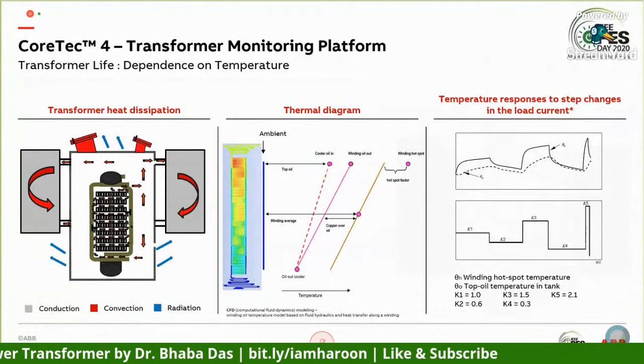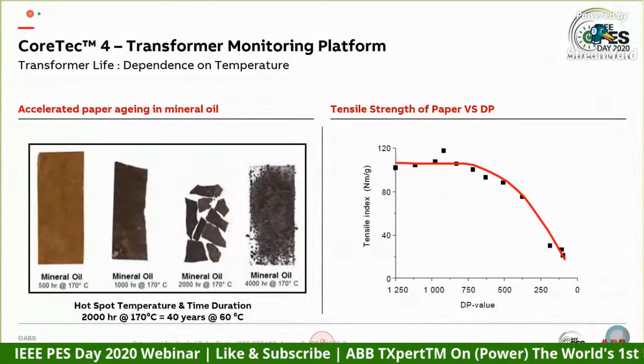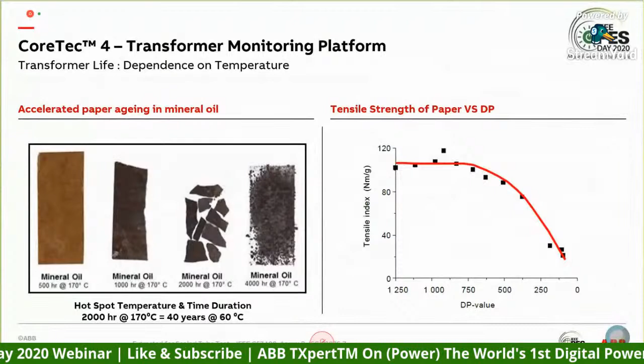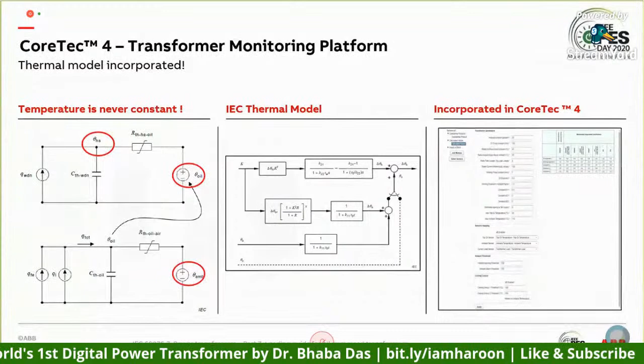What we are trying to calculate is, if you have the online DGA sensor with the moisture figures, with the temperature, how long it takes to fall to 200 DP. I think all of you know that the end of life of a transformer is considered to be around 200. That is something we are trying to calculate in the CoreTec 4. And we know temperature is never constant, so we have uploaded the entire IEC thermal model. And as I mentioned before, all the transformer specific characteristics is now part of the brain. And that is how we calculate a lot of different features for all of you.